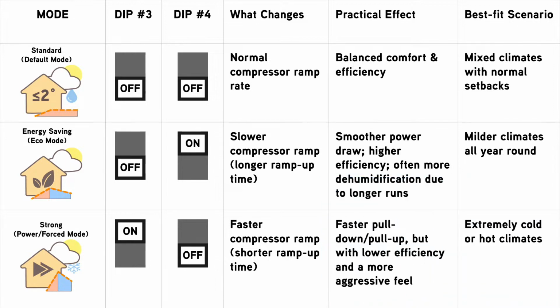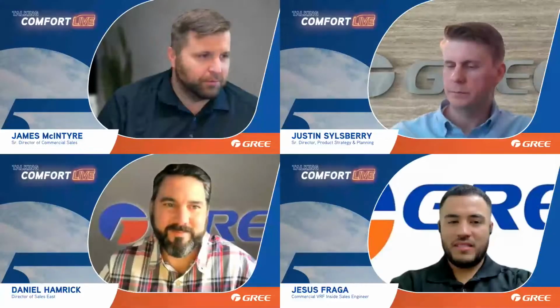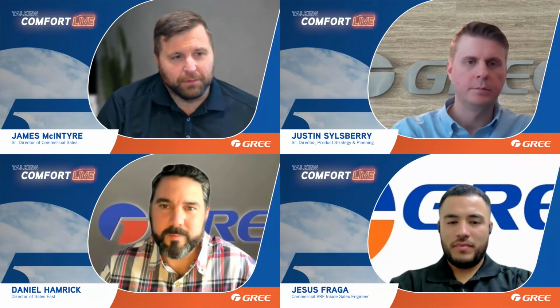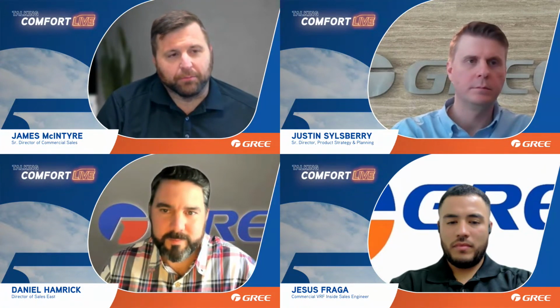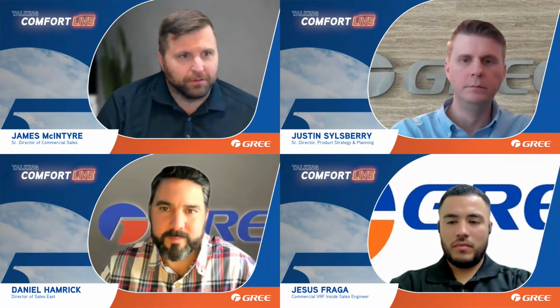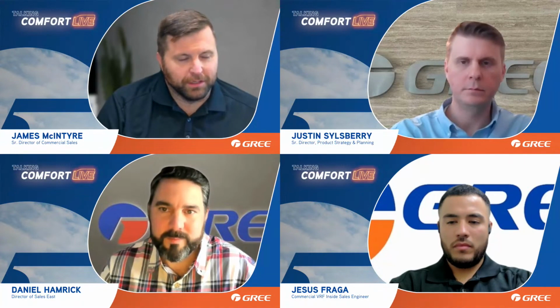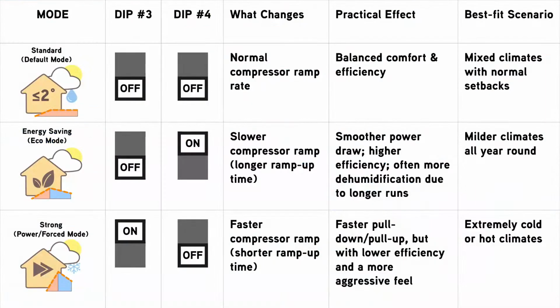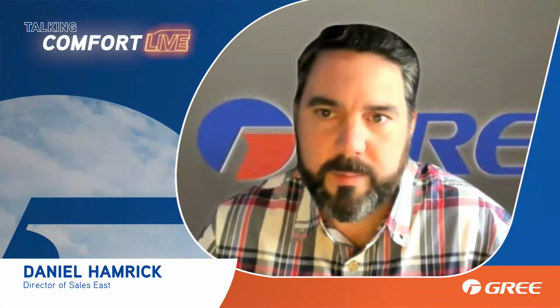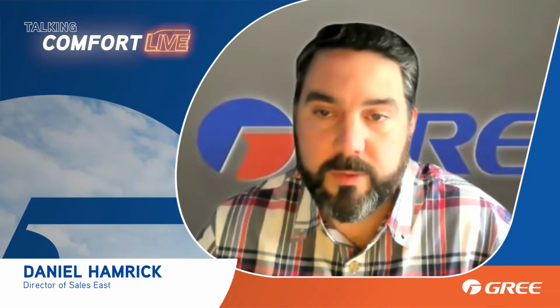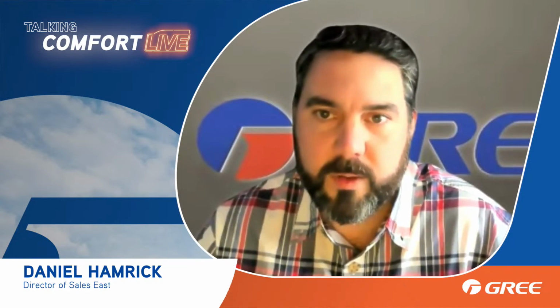If you did your heat load calculation like everybody does all the time, right? If you do your heat load calculation to determine that you might need 32,000 BTUs, well, you might be able to use eco mode and you meet your set point during its ramp up time. So it never has to hit like 36,000 BTUs to provide the cooling needs or heating needs for that space. So that's a good option to use. Would you guys agree with that, using eco mode for fractional changes? Yep. That's actually listed on the Flex Quick Start Guide. It describes how to use it for those half ton increments.